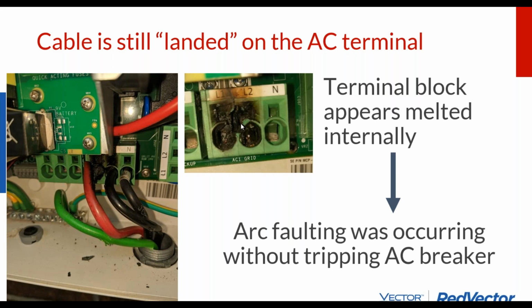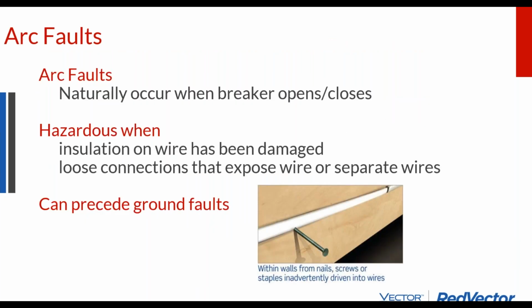So this inverter was on a breaker, but the electrical issue is going on. Well, it can or it couldn't. We have to go and look at how breakers work, and these arc fault detecting breakers are a little more advanced than just a breaker you put on a solar inverter. And so it's like, well, why did the arc fault detection in this inverter not trigger when an arc fault was occurring? And the answer is, well, because their arc fault detection is on the DC side, it's not on the AC side. So we had an AC arc fault that wasn't on an arc fault breaker, and it's not being detected by the arc fault detection in the solar inverter. This is a workmanship issue.